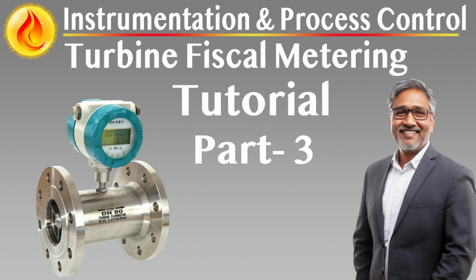Density measurement, real-time mass conversion and cross-validation with dual densitometers. Each fiscal metering system must include a dual vibrating tube densitometer system installed on a slipstream taken from the metering station header. This configuration allows continuous density measurement of the process fluid under representative conditions without interfering with the main flow path. The use of 2 densitometers operating in parallel enables real-time comparison and fault detection.